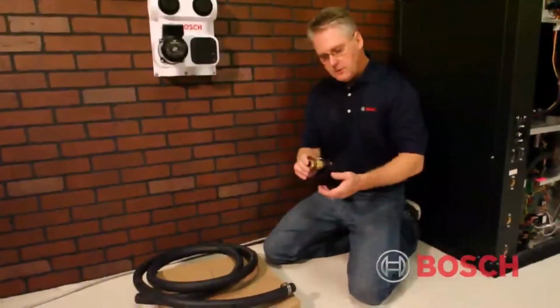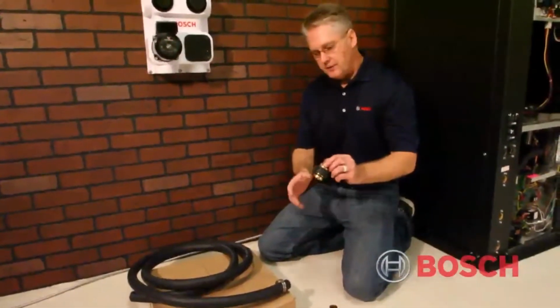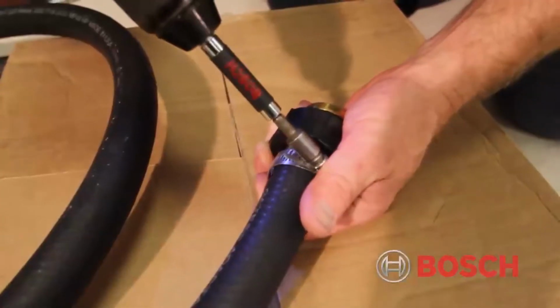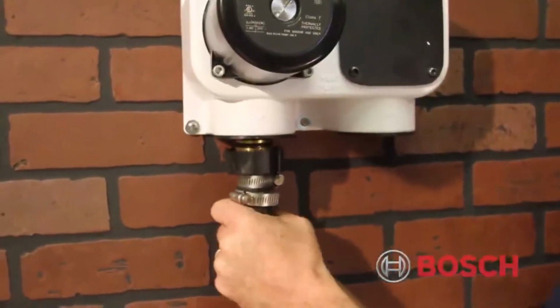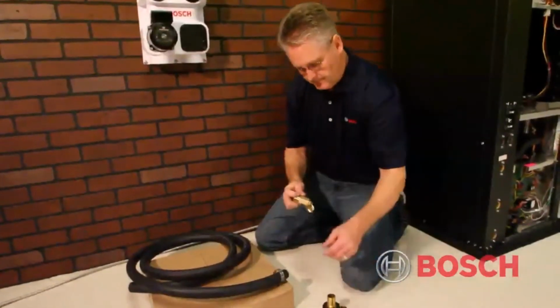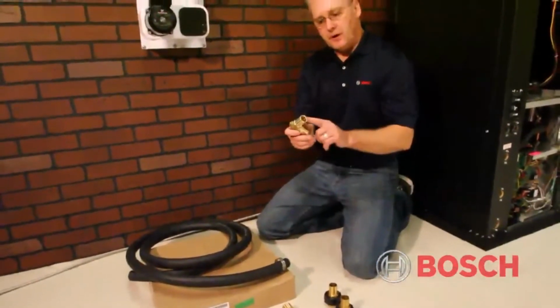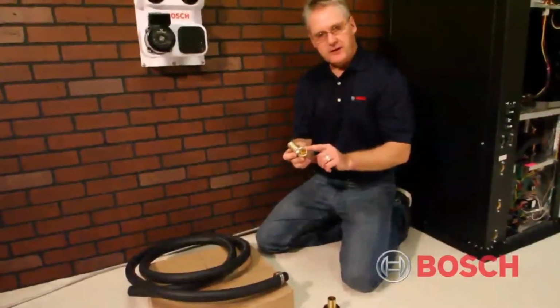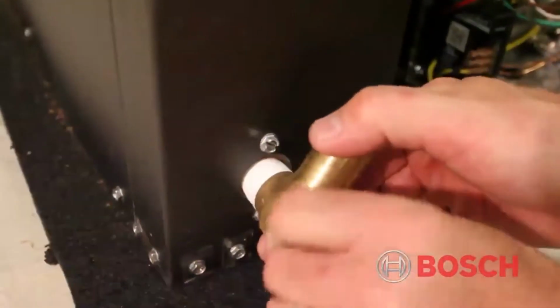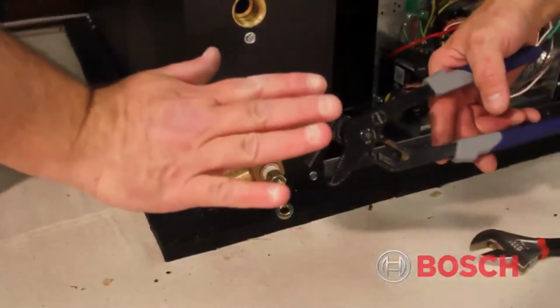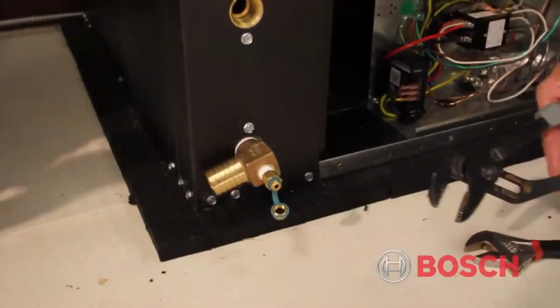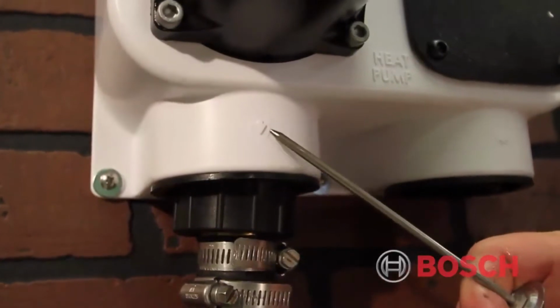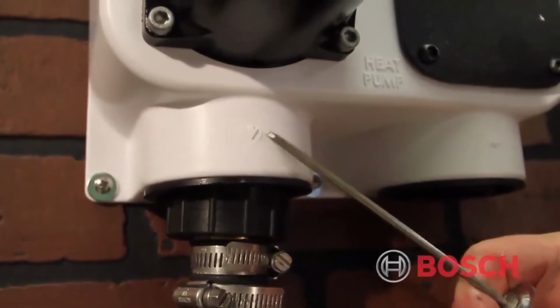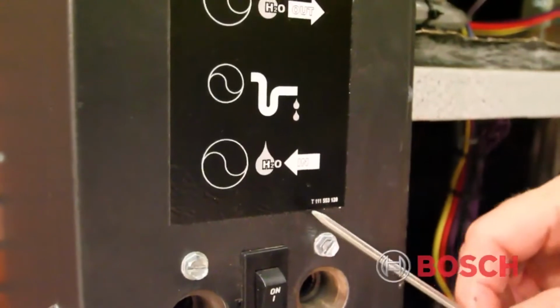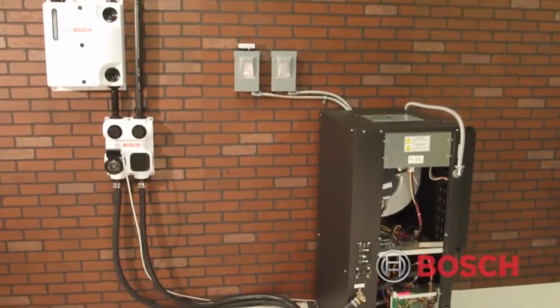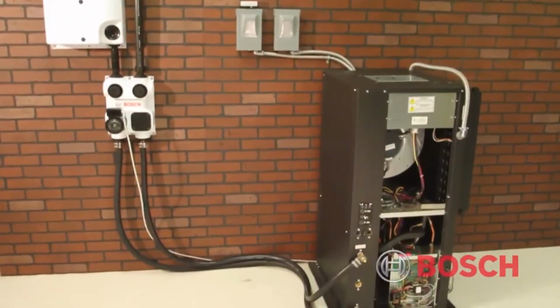Inside the box are double O-ring fittings to barb. The barb fitting is going to go on the hose. The double O-ring fitting is going to go inside the flow center. Also inside the box are the elbows. Barb fitting goes onto the hose. This fitting is going to get Teflon taped and go into the geo unit. Never use adjustable style grip tools. Always use the proper tool on the brass fittings. It's important to make the right water connections. Always verify the water flow on the flow center and the water flow on the unit is correct. The hose may need to be insulated to eliminate condensation issues.